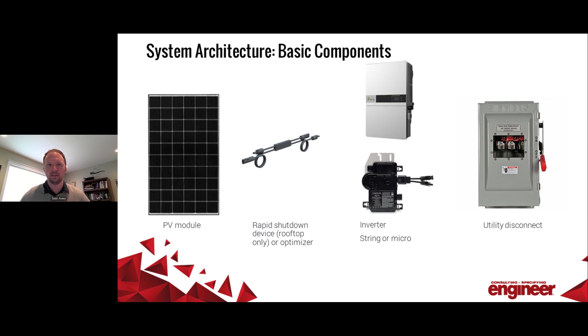Here's an example of a one-line diagram for a string inverter. I'm not going to spend a whole lot of time here, but I want to make a few points on here. So we have our solar modules, which produce a DC voltage of 50 volts plus or minus 10 volts, just depending on the configuration. And generally what we'll do is we'll string them in series, kind of like Christmas lights, up to a point where on the DC side we're achieving voltage around 1,000 volts. So in this version here, it's probably a little hard to read, but I have 18 modules in a string.